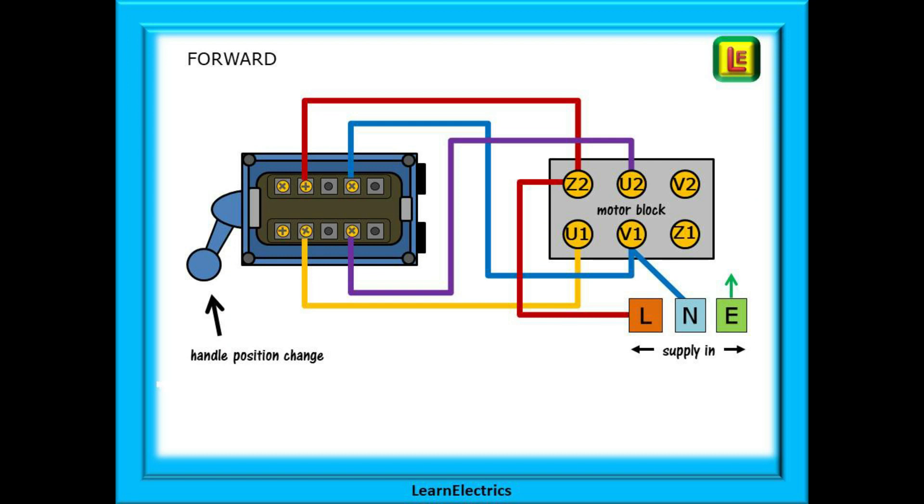Now what happens if we choose the forwards position? Visually the only change is that the selector arm has changed position. All the contact changes have taken place internally. If we could see inside the switch we would see that the straight through connections have been made as shown here by the dotted lines the internal connections. Phase connects to U1 and neutral to U2 and hopefully the motor turns in the forwards direction.